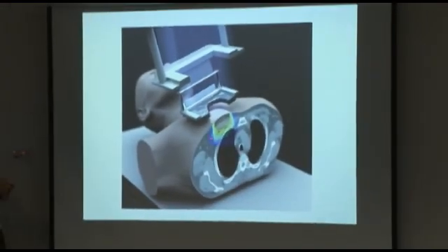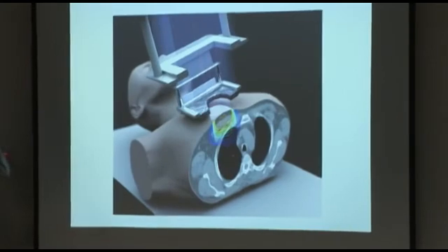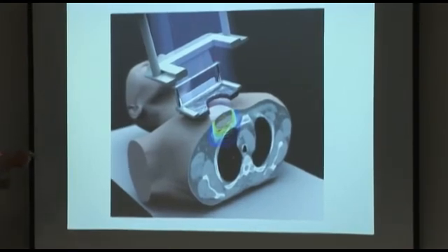So here's an example of what a physical cutout looks like. This is actually an electron treatment, so let's not worry about the types of particles being used here. But here's a lead block. What the doctor presumably wanted to treat was a region in there. This was made out of a lead-like material called cerrobend, and it was shaped in accordance with the treatment plan.